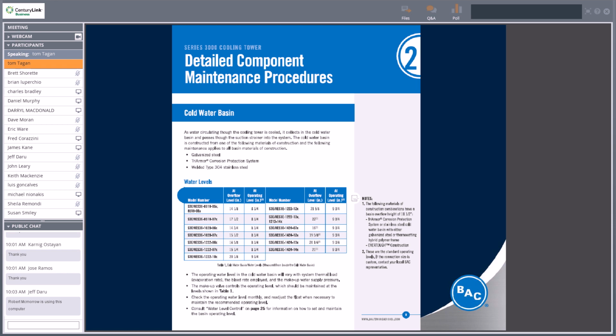The next page lists all the model numbers and the operating level, water level recommendations. Your cold water basin in this particular type of tower is gravity feed. So we're going to recommend there's a minimum and maximum level. I believe it's 2 and however many inches. For these particular units, you'll see 8 3/4 inches to 9 3/4 inches. That will ensure proper flow over your fill. It's important to make sure we have nice, even fill distribution over the fill of your cooling tower. And again, we'll discuss that in depth a little bit more later.